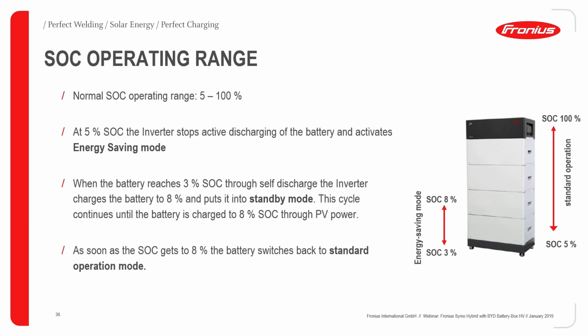If it gets down to 5%, the inverter stops actively charging or discharging the battery and goes into an energy saving mode. If there's not enough excess and the battery self-discharges over a long time down to 3%, the inverter will try to charge it back up to 8% and put it into standby. This continues to make sure it stays at 8% if it gets too low. Once it hits 8%, it goes into its normal standard operating state rather than the energy saving mode.